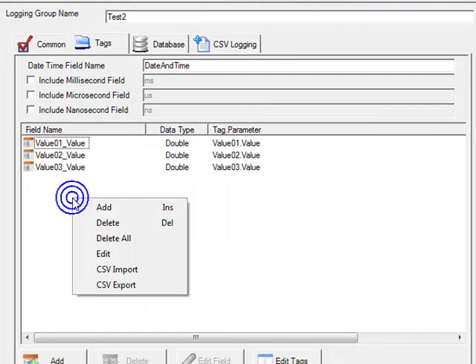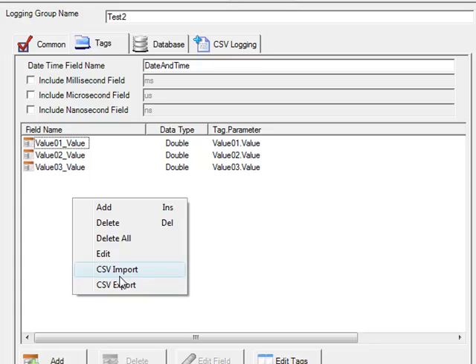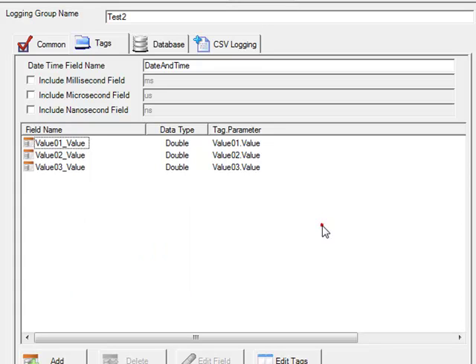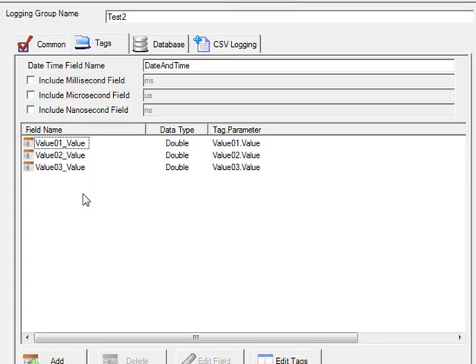Remember that you can right click on the field list and perform a CSV export and CSV import if you need to set up multiple tags. But do remember to not use spaces, commas, dashes, or periods in any of your field names, anything that a database engine would not like. OPCSystems.net tags do allow spaces, but third-party reporting products typically do not like spaces in field names.